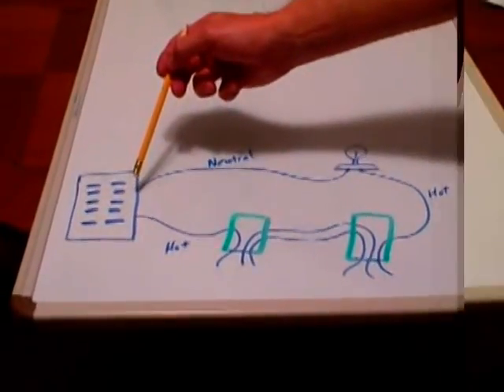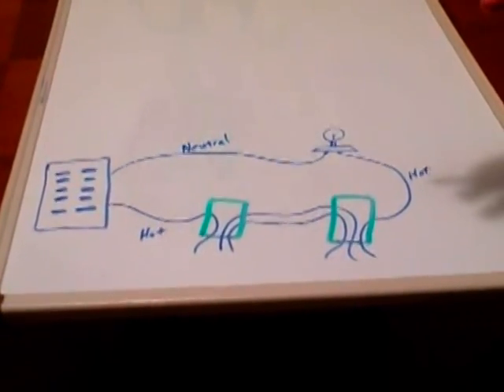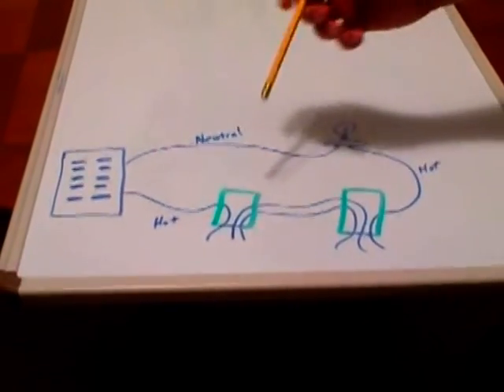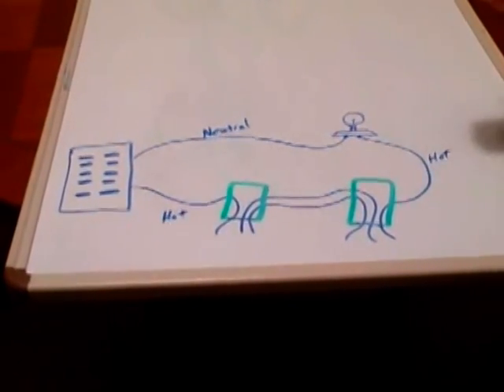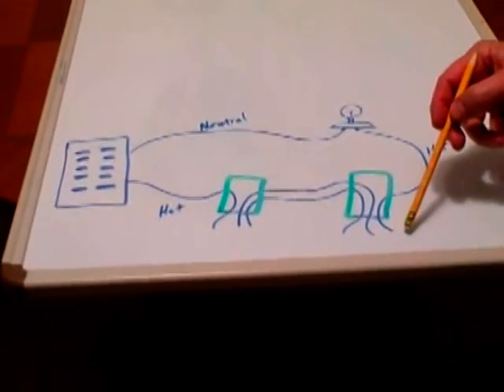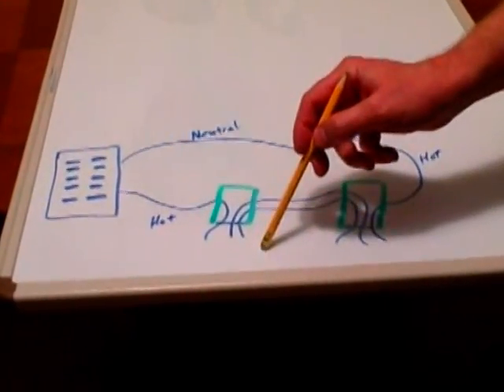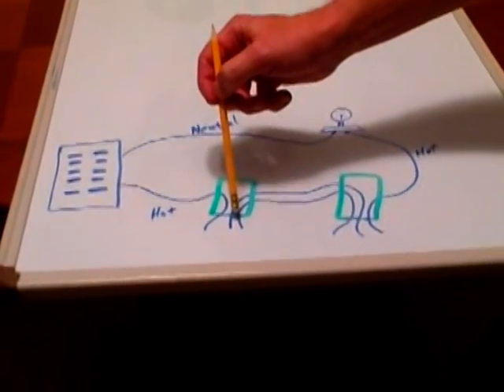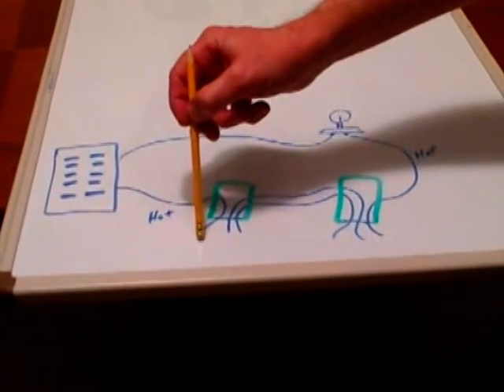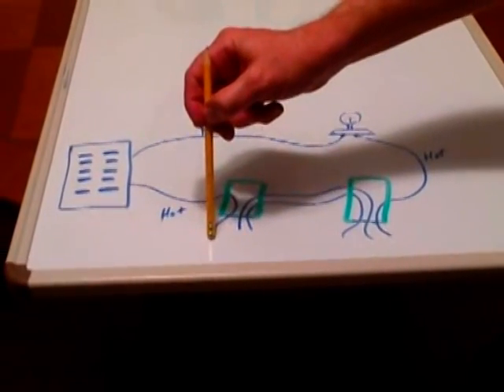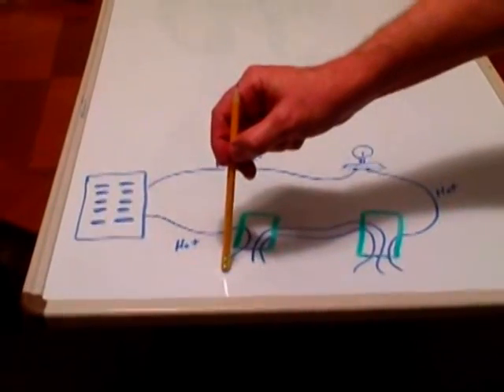To find the first common, we're going to need to turn the electric back on so you're going to have to be very careful here and make sure the wires are all separated and not touching anything. Once you turn the electric back on, use an electrical tester and test each wire to find which one's live. In this case, you're going to test all these and none of them will have any electric flowing to it. This wire will. So this is our common. This is the wire that's going to go to the first dark screw, the common screw on the first three-way switch.